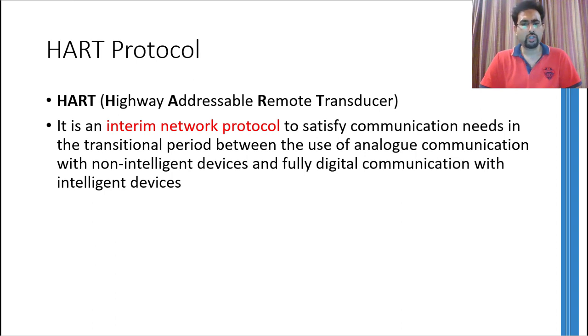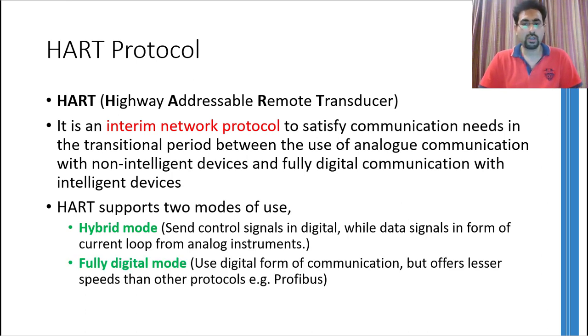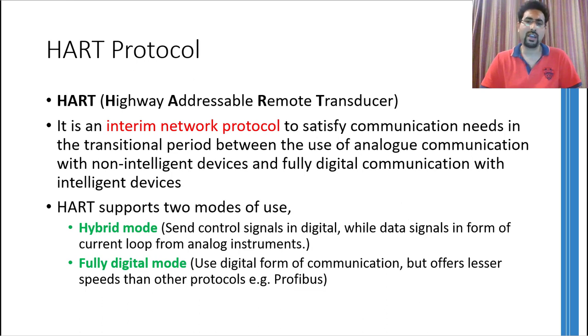At the start of the lecture, I talked about protocols which handle both analog and digital information transfer, because we are still using analog devices and need to route analog signals through networks. This protocol is called HART protocol, which stands for Highway Addressable Remote Transducer Protocol. It is an interim protocol used in two different modes. One mode supports both digital and analog communication, specifically for devices which generate analog signals — the signals are routed using a 4-20 mA signal, whereas the control signal is in digital form. The second mode is called fully digital mode, where devices communicate through fully digital signals, though the speed of communication is lesser than other fully digital protocols.